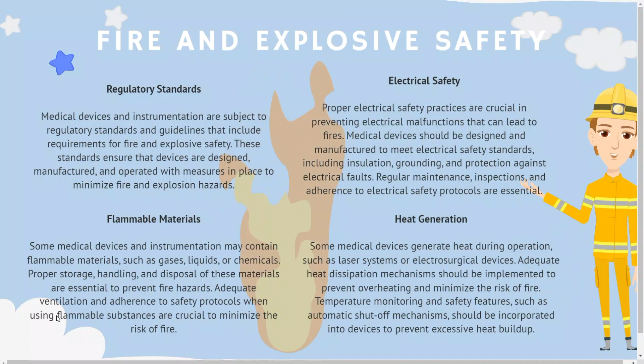Last but not least, heat generation. Some medical devices generate heat during operation, such as laser systems or electrosurgical devices. Adequate heat dissipation mechanisms should be implemented to prevent overheating and minimize the risk of fire. Temperature monitoring and safety features, such as automatic shut-off mechanisms, should be incorporated into devices to prevent excessive heat buildup.